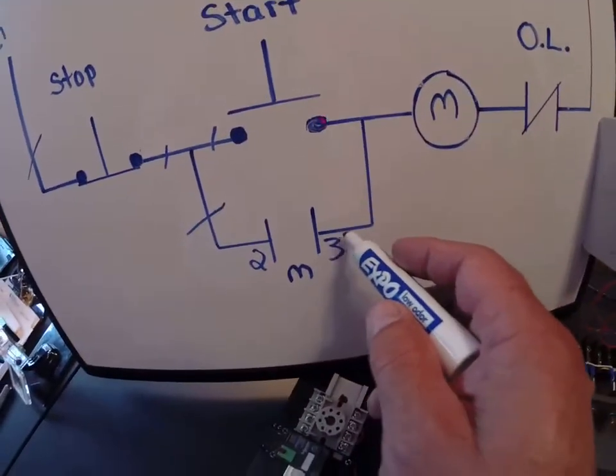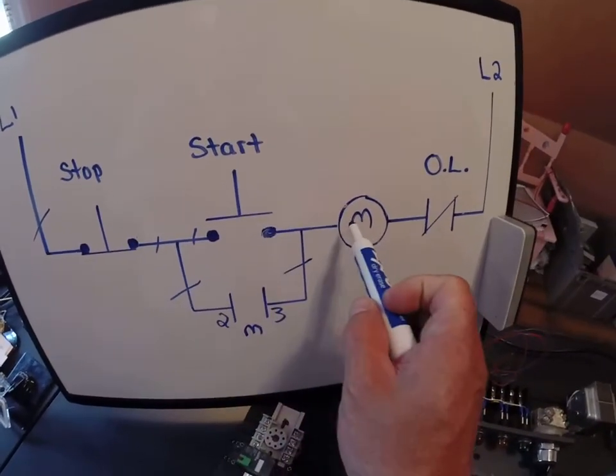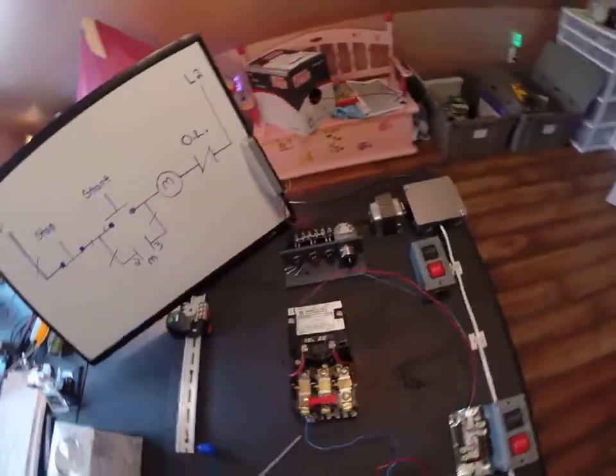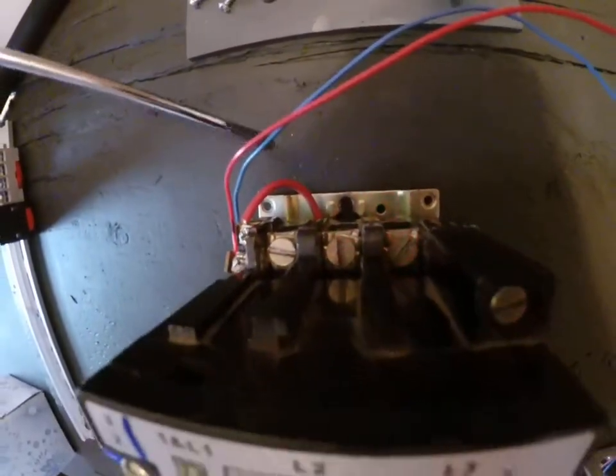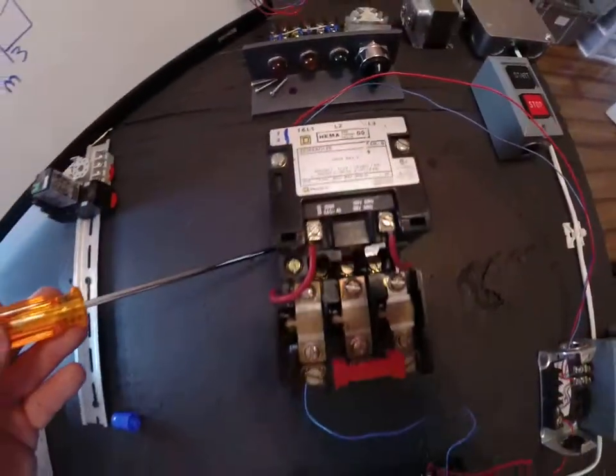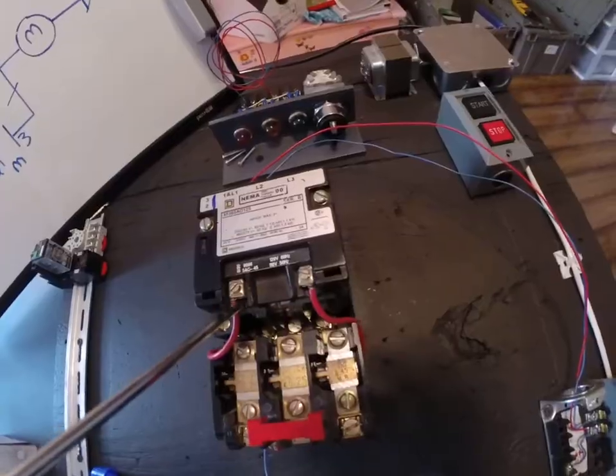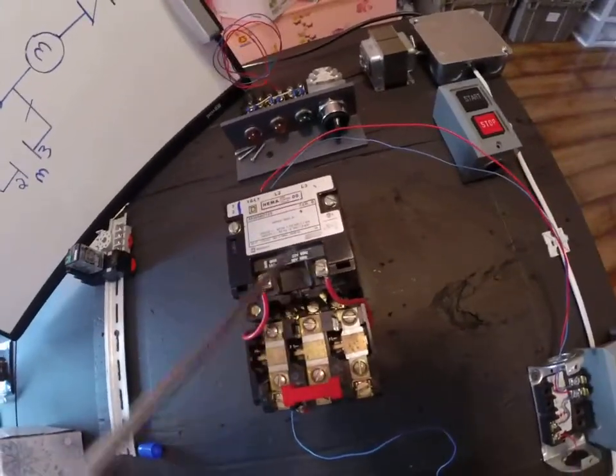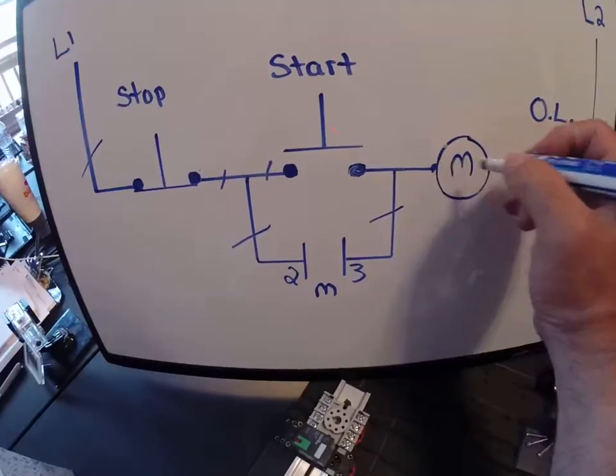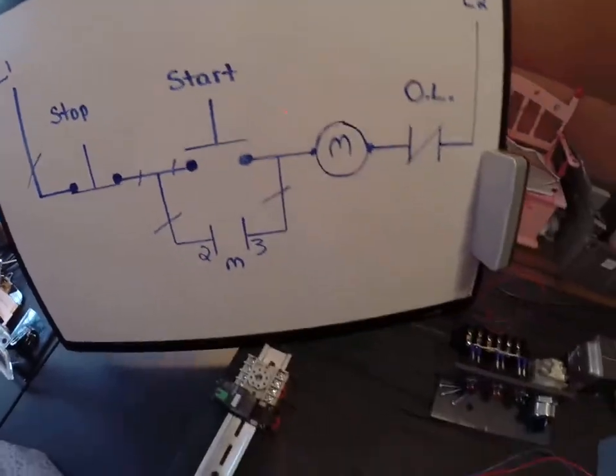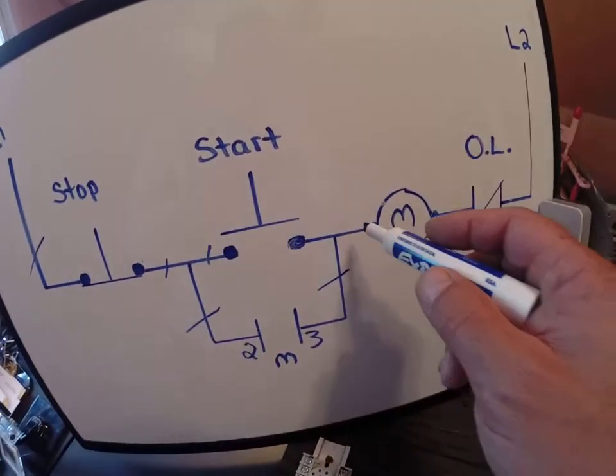I still need another wire from here to the coil. That's a cool thing from the factory—they actually provide that wire right here, this big red one. They give you this from the factory because they know you need it. This wire sneaks around the back of the starter and sneaks up to the front and goes to the coil. These two screws represent the coil for this starter, so I'm going to draw screws in here so you're aware that they actually exist.